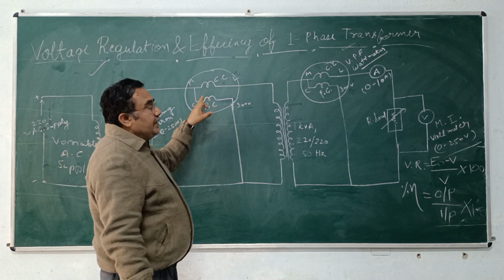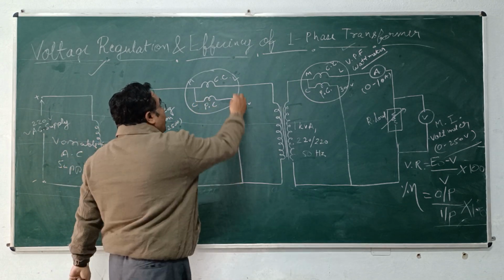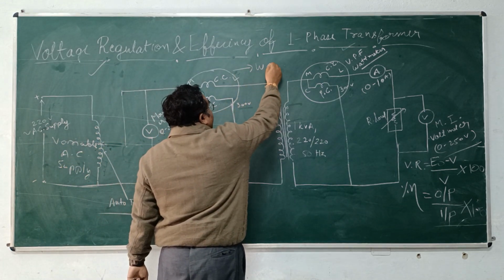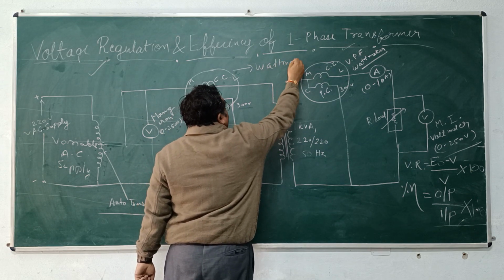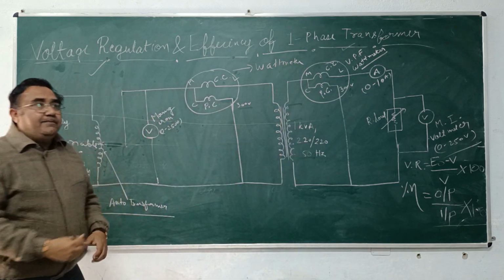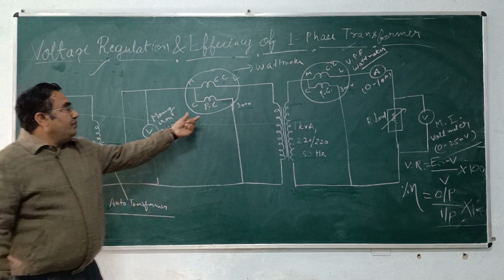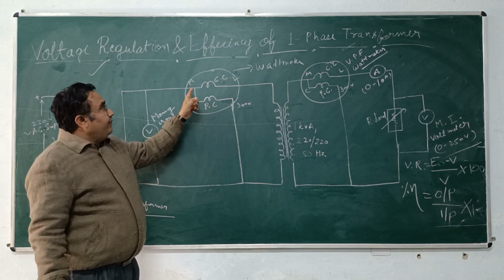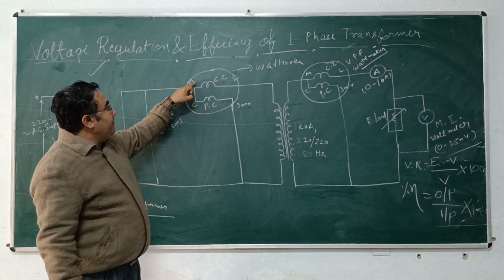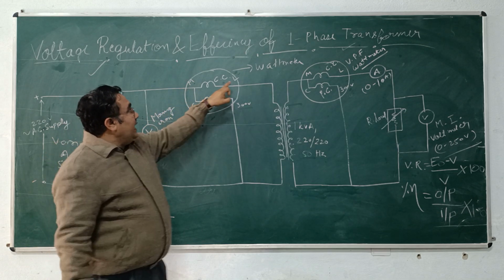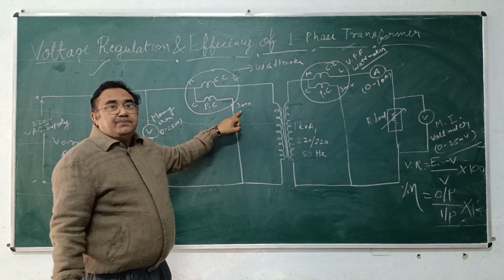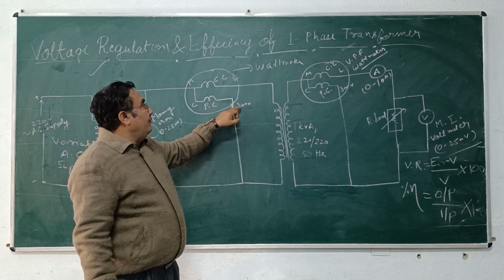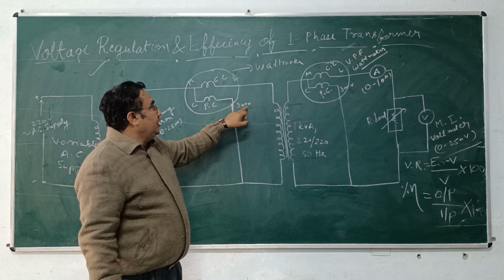Now we have to measure the input power also. For input power, we have an instrument called a wattmeter, since power is measured in watts. It has 4 terminals: M, C, L, and a voltage point, generally marked 0 and 150 volt or 300 volt.